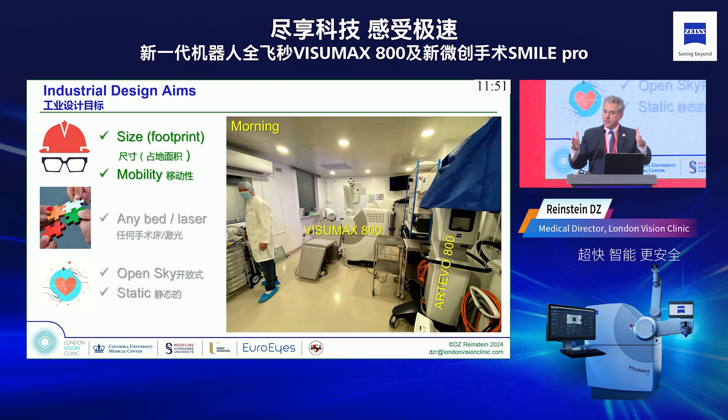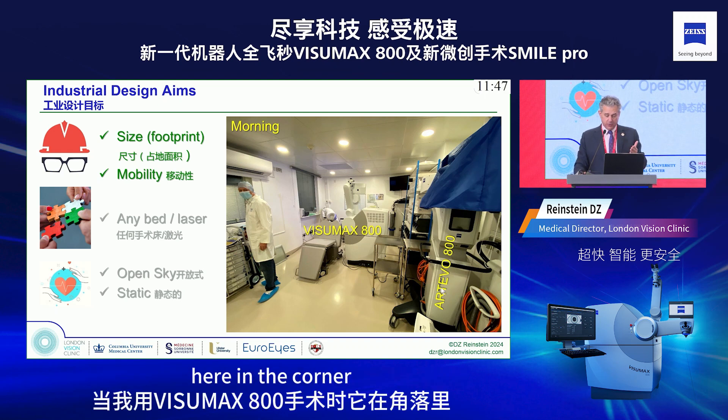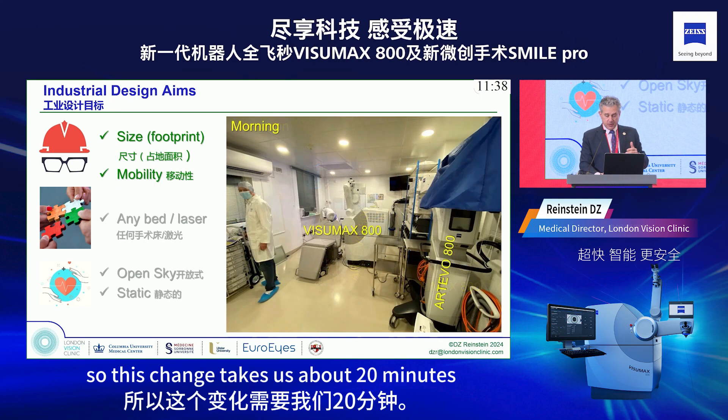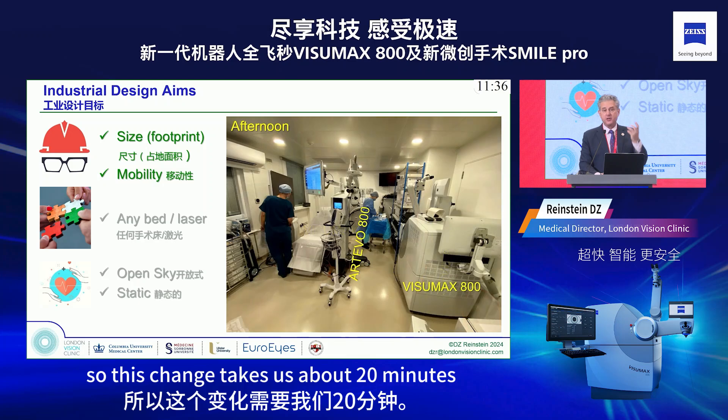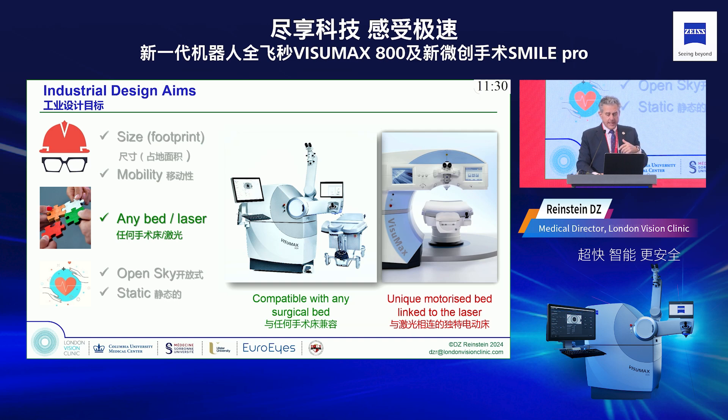This is one of my operating rooms in my clinic in London — our cataract room is very small. You can see I have my Artevo 800 in the corner when I'm doing VisuMax 800 treatments, and in the afternoon when we do ICLs we just switch the instruments around. This changeover takes about 20 minutes because the machine rolls on wheels.